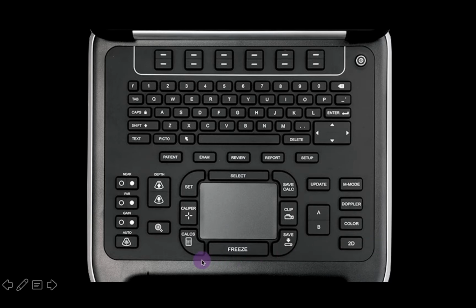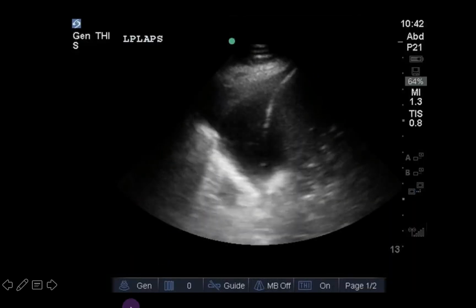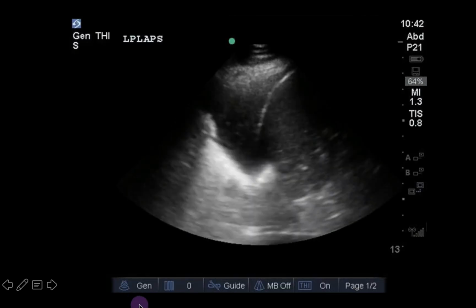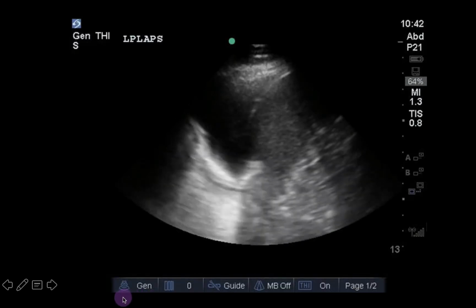Next, let's go over the controls of the ultrasound machine, or what is sometimes referred to as knobology. The location and assortment of knobs and buttons will vary from machine to machine, but most will have the same ones. Starting from the top, these buttons allow us to adjust functions that will be displayed at the bottom of the screen. These vary depending on the mode, but often include the level of penetration desired: general, resolution, or penetration.